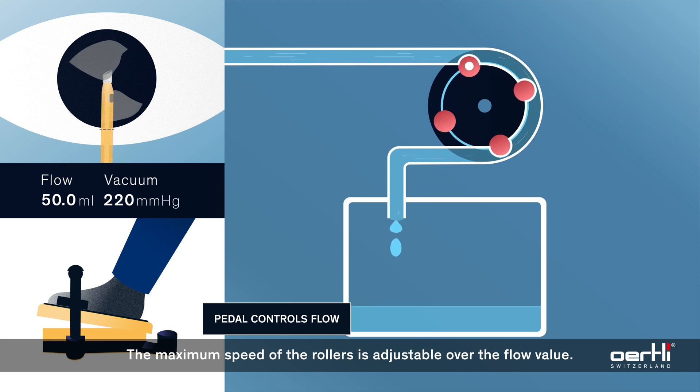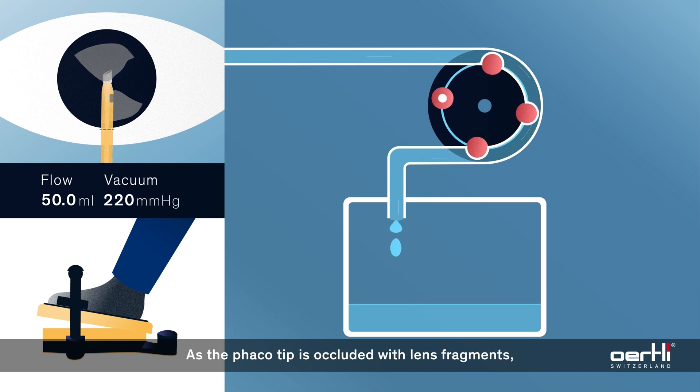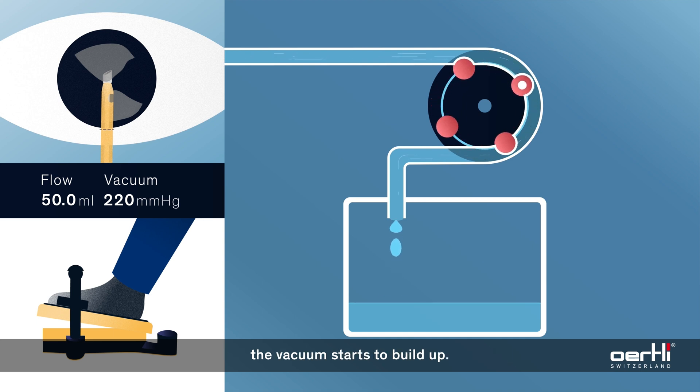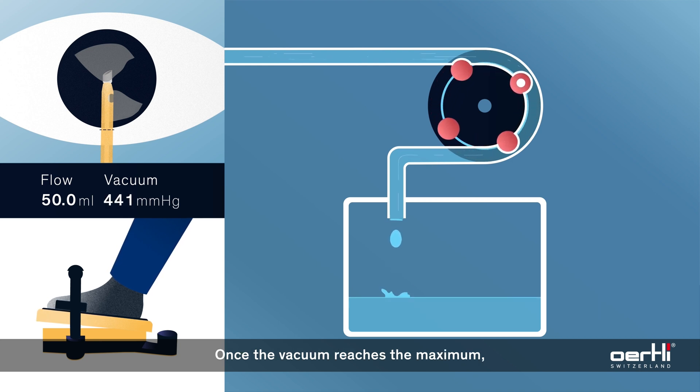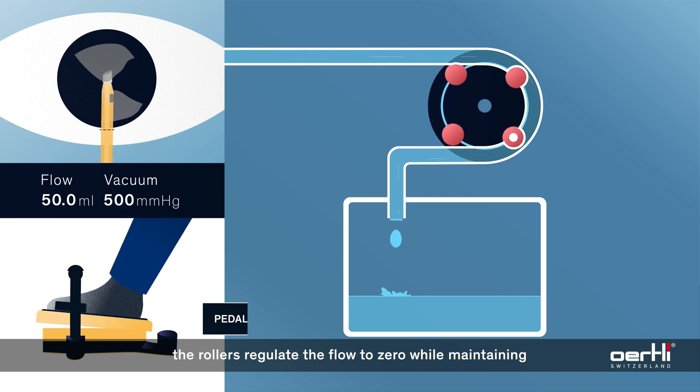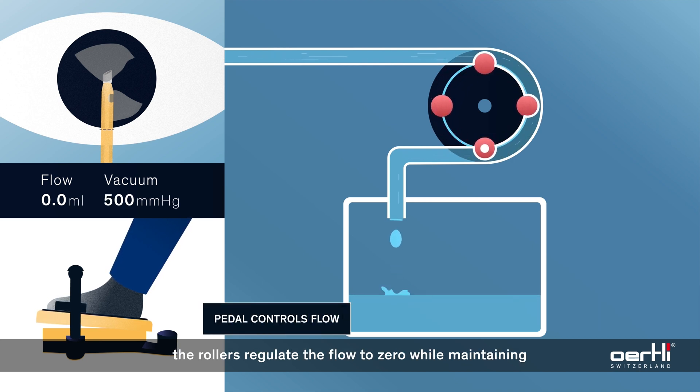The maximum speed of the rollers is adjustable over the flow value. As the phaco tip is occluded with lens fragments, the vacuum starts to build up. The higher the flow value, the faster the build-up of the vacuum. Once the vacuum reaches the maximum, the rollers regulate the flow to zero while maintaining the vacuum to securely hold the fragment.